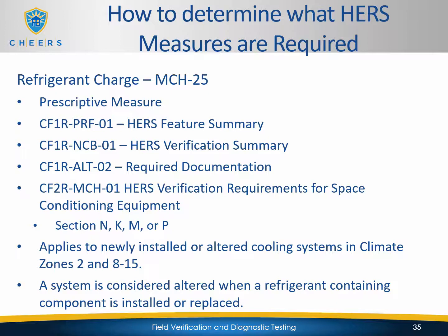So these newly installed or altered systems, a system is going to be considered altered when a refrigerant containing component is installed or replaced. So if that component has refrigerant going through it, it's going to be considered a refrigerant containing component. They're going to have to draw down and remove all the refrigerant out of that system to replace it. That's going to be considered an altered cooling system. And then if you're in climate zones 2 and 8 through 15, refrigerant charge is going to be prescriptively required.